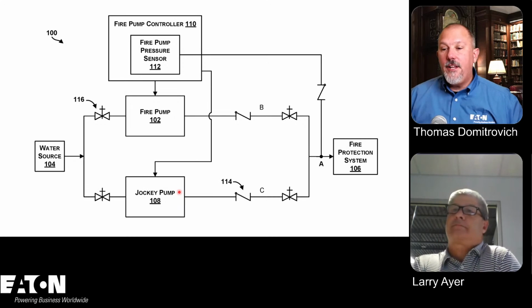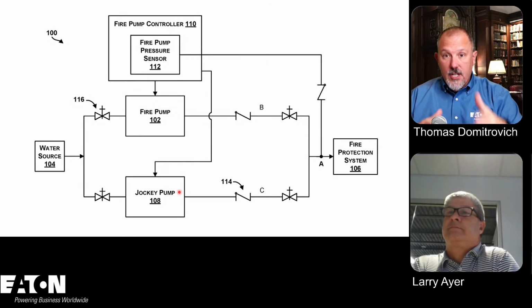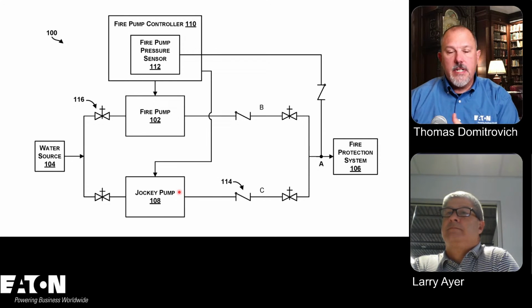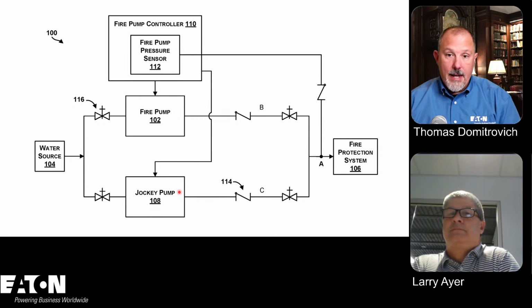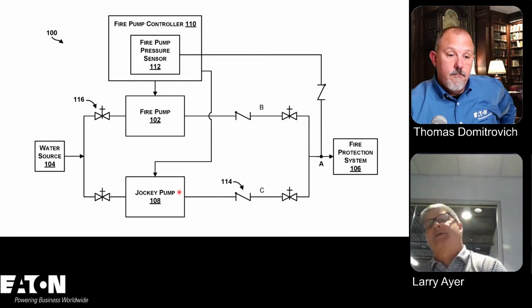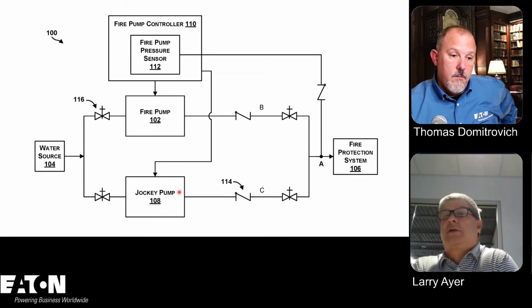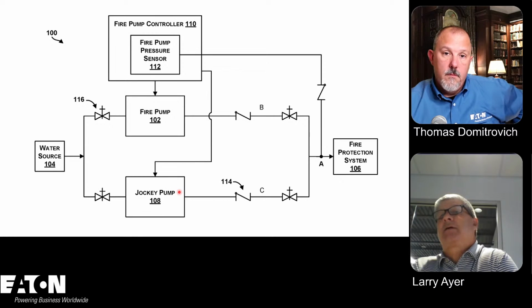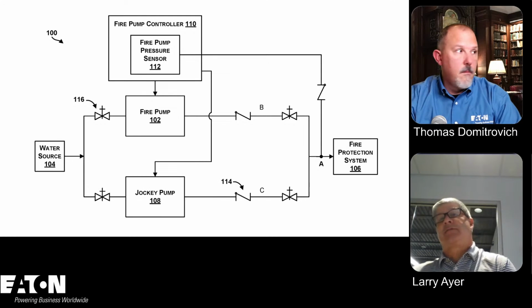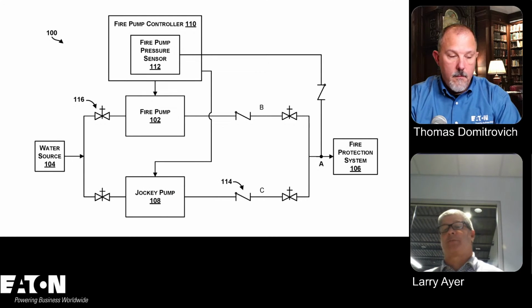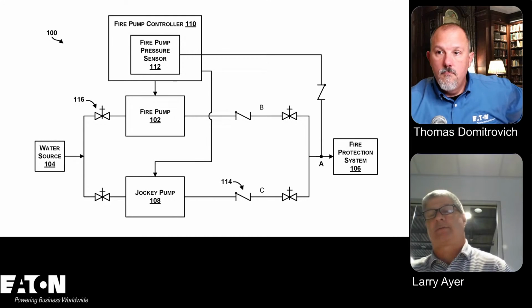Yep. And if you think about it, we're going to talk about the reliable power source, how we size everything and how we protect everything. So if that feeder goes down, that means you lost your fire pump. You lost your jockey pump too, but you're not going to have one without the other. Right. And basically, the bottom line is the jockey pump's there just to maintain pressure. So when you lose power, once that pressure is lost, the fire pump takes over. And that's where you really want to have that backup generator and all the extra components to have the 2-hour rating and things of that nature.